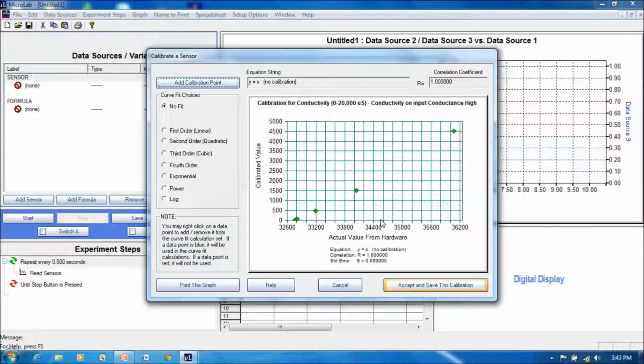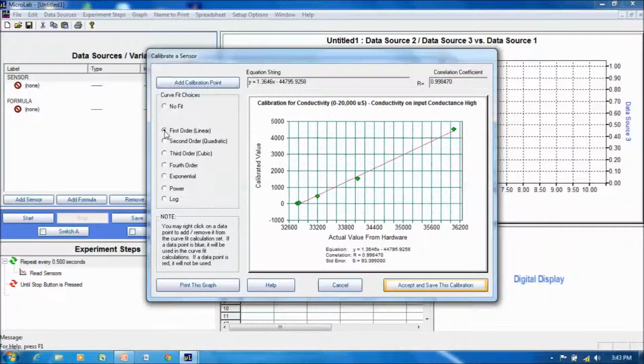There we have it. We have actually 5 data points, counting the deionized water. We could try a first order fit, and we can see that that's not that bad, but it's not particularly great. Since we have 5 data points, we could actually try a second order fit that seems to be much better. Let's go back to the first order fit just for the sake of argument. With the first order fit, the slope of the line, which is your calibrated value in microsiemens per centimeter versus the actual sensor value, let's call that conductance, that ratio of y over x, the slope, is the cell constant.